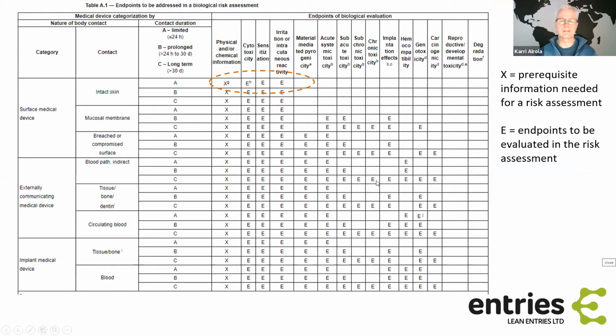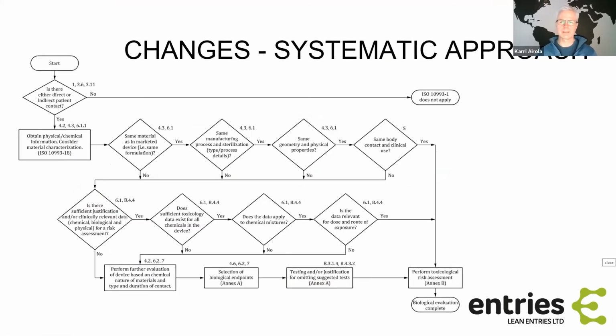But this is then to be done together with your service provider. This table, at least in this annex of 10993, helps you in the design phase to make some estimates on what is the most probable test package you would need when doing the biological safety assessment. And should there be some changes in your device at later stages, this 10993 also gives you very good help in terms of the decision tree.